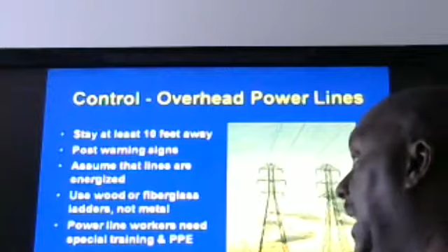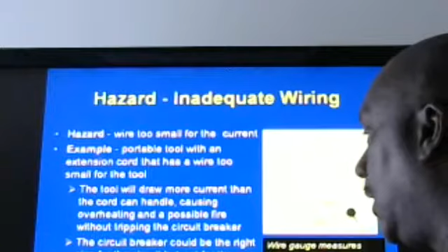So, hazardous or inadequate wires - we talked about this. If the wire is too small for the current being pulled through, like the tool draws more current than the cord can actually handle, it causes the cord to overheat, possibly causing fire. The circuit breaker could be the right size for the circuit but not for the extension cord.